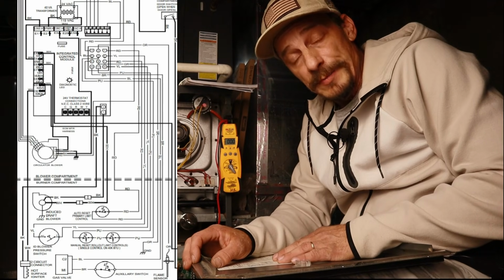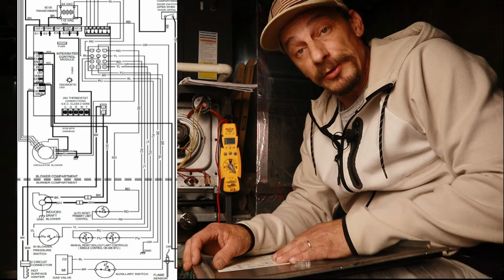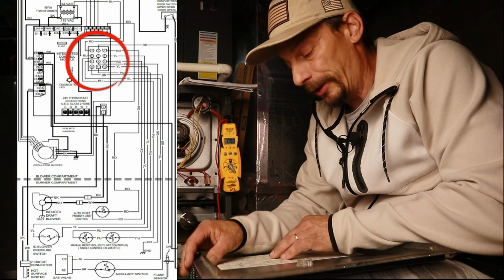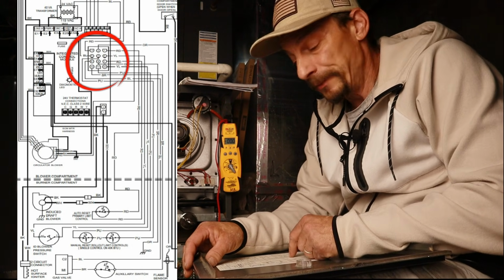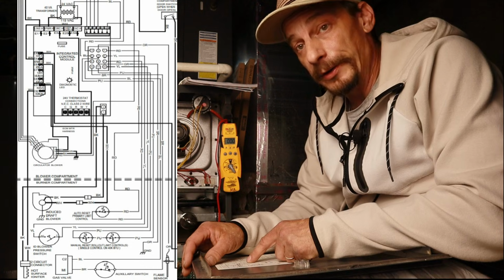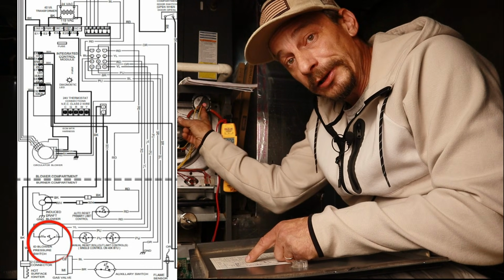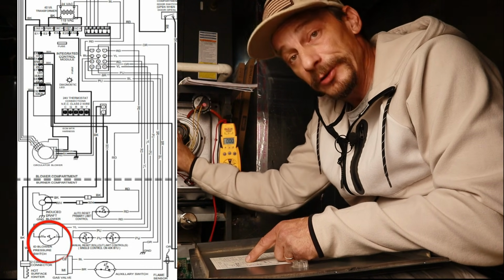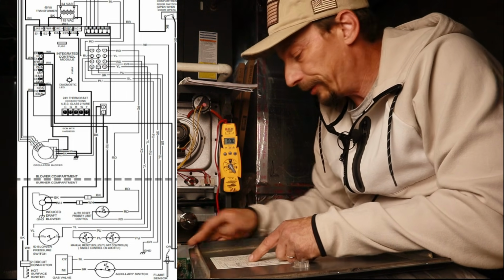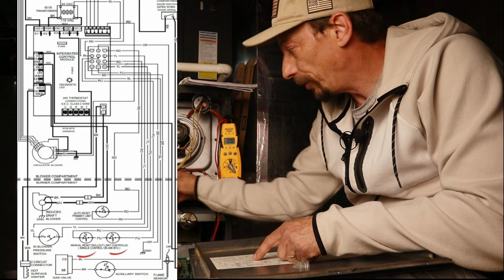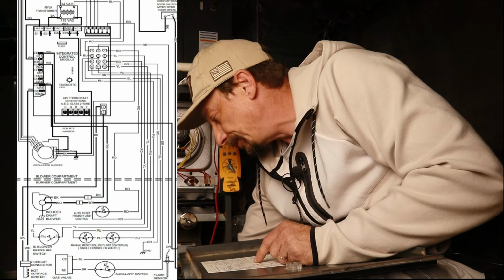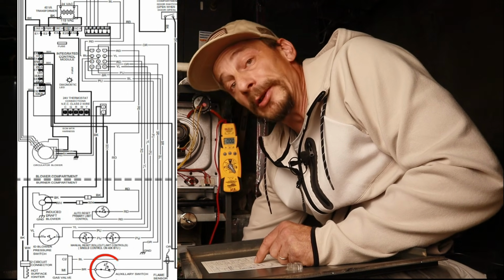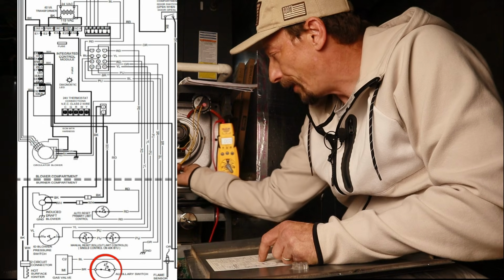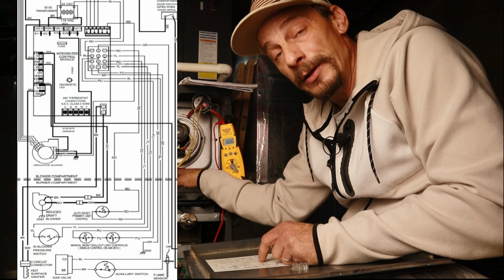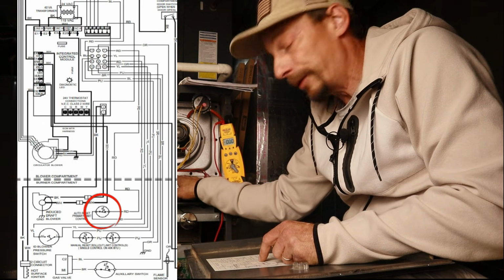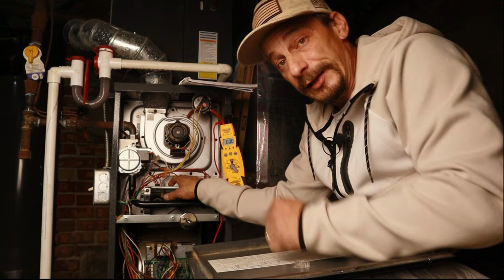Now let's look at the schematic again, and when you look at it, you'll see that there's a whole bunch of wires coming out of that Molex plug, and all those wires are going to safeties. So we have a pair of yellow wires going to our pressure switch here, and that is the safety to tell us the inducer motor is running. We have wires coming off of that going to our flame rollouts. We have wires coming off of it to go to our thermal limit switch on our blower casing. We also have wires coming off of that going to our main thermal limit, which is the temperature probe that goes into the heat exchanger.